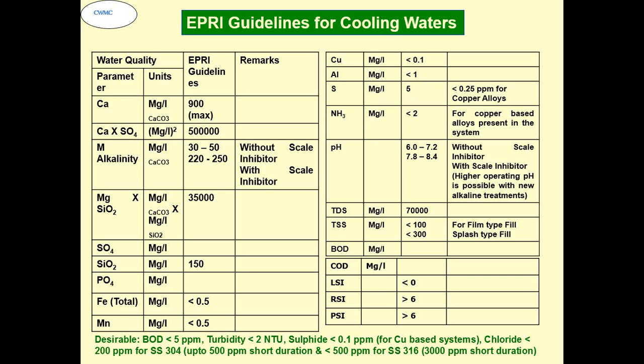Magnesium times silicate not more than 35,000, silica less than 150, total iron less than 0.5, total manganese less than 0.5. BOD, of course, is not mentioned here, but I put it in green. Less than 5 ppm BOD is a good measure for the water to be used, because it will be more required when we use sewage treated water as makeup to the cooling water system. Turbidity should be less than 2 NTU. Sulfide, if copper based systems are there, should be less than 0.1. Chloride less than 200 ppm for SS304, and up to 500 ppm for short duration; 500 ppm for SS316, and up to short duration even 3000 can be tolerated.